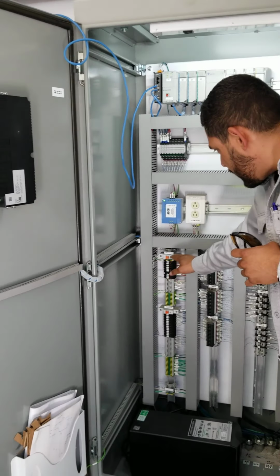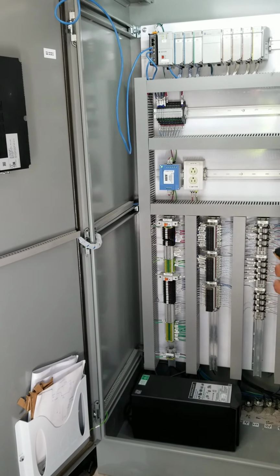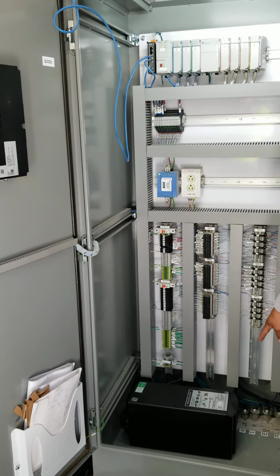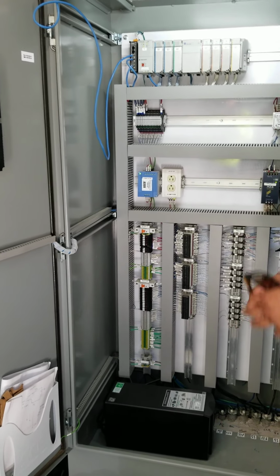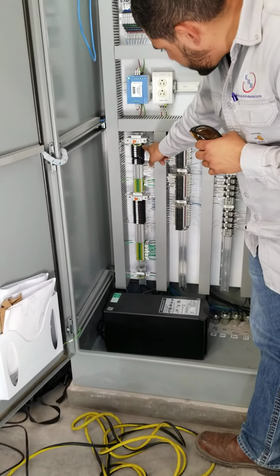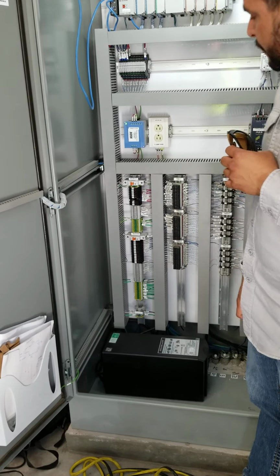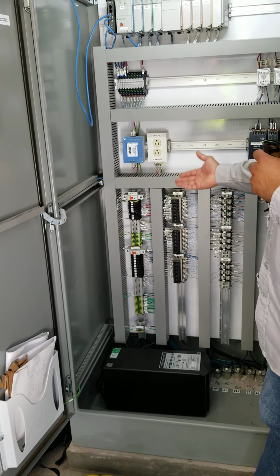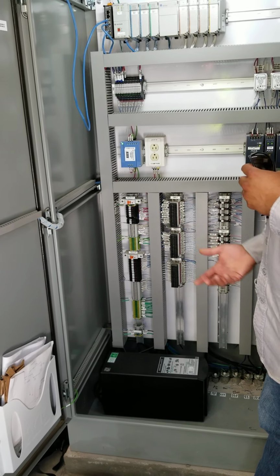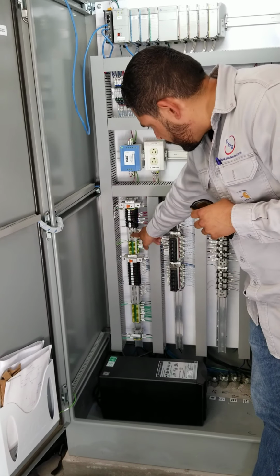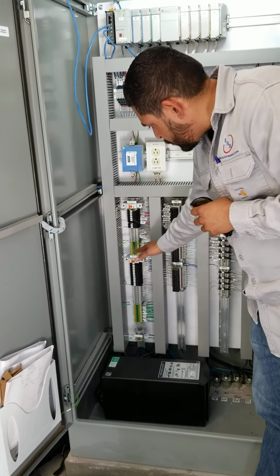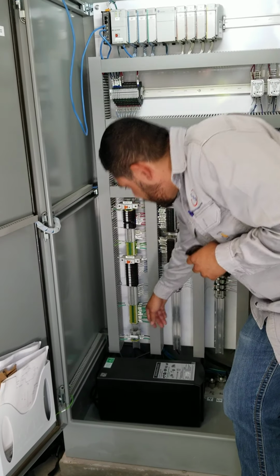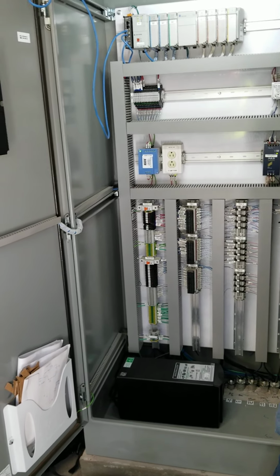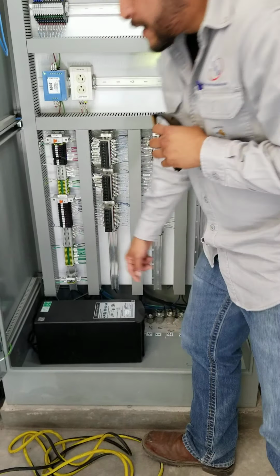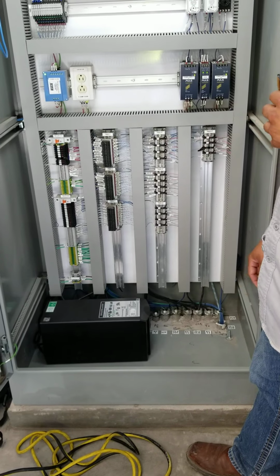In this section, we have our main circuit breaker, which is your 120 volt AC, which is being supplied by the UPS. We have our sections of fuses for every device that has a 120 hookup to it. We do have secondary fuses for more protection on it. Your neutral and your ground. This is your 120 AC. This is your plus and minus 24 volt DC bus. Again, we have a main circuit breaker, and then we have secondary fuses for more protection to your devices.